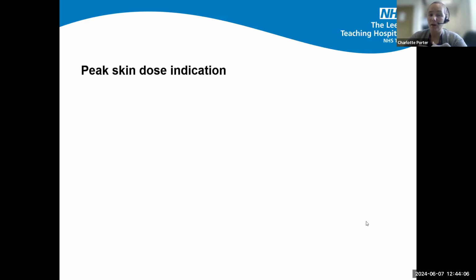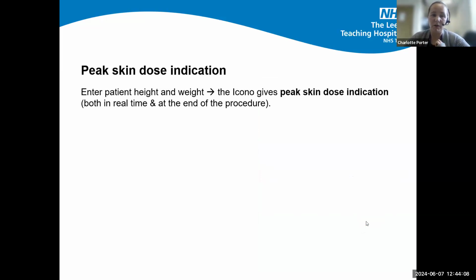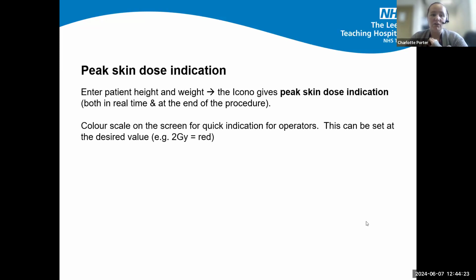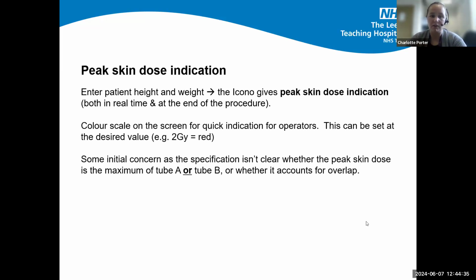So I wanted to talk a bit about the peak skin dose indication as well. If you enter the height and the weight of the patient when you're registering them, then the Icono will give you a peak skin dose indication. This happens both during the procedure and also at the end of the procedure. There's a color scale on the screen, and it gives a quick indication for the operators. I think this can be set at any value you want. So that's quite a useful quick check for the radiologists or cardiologists who are using the system.